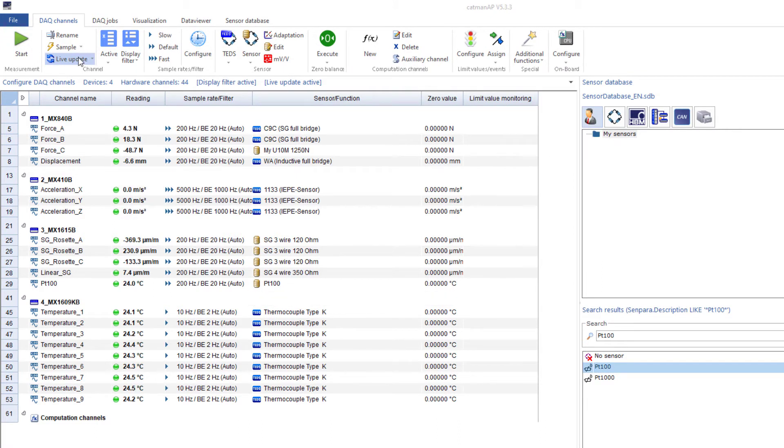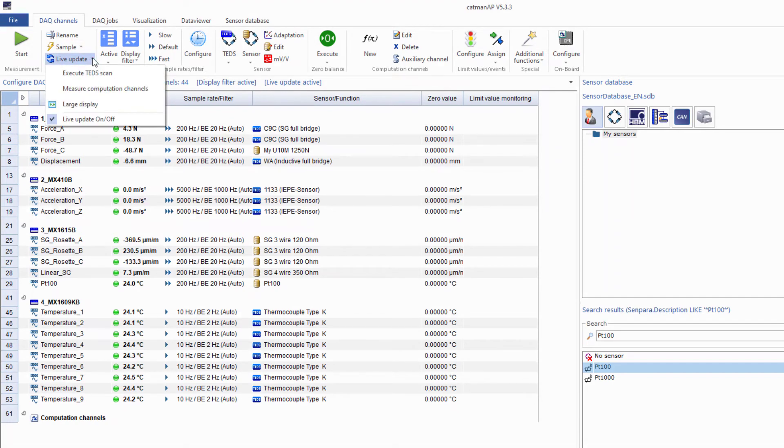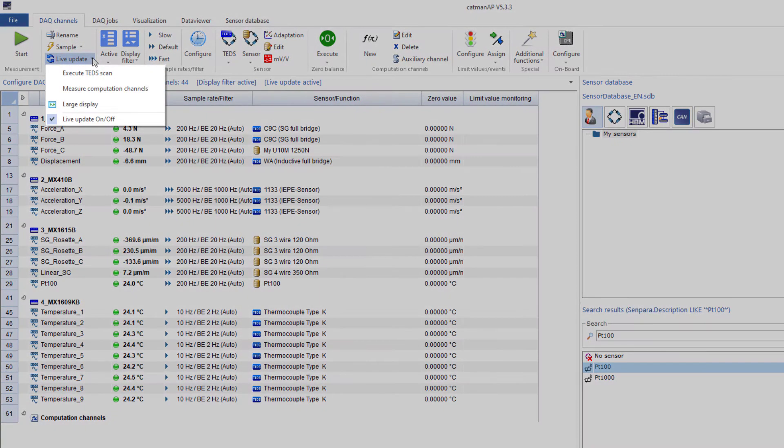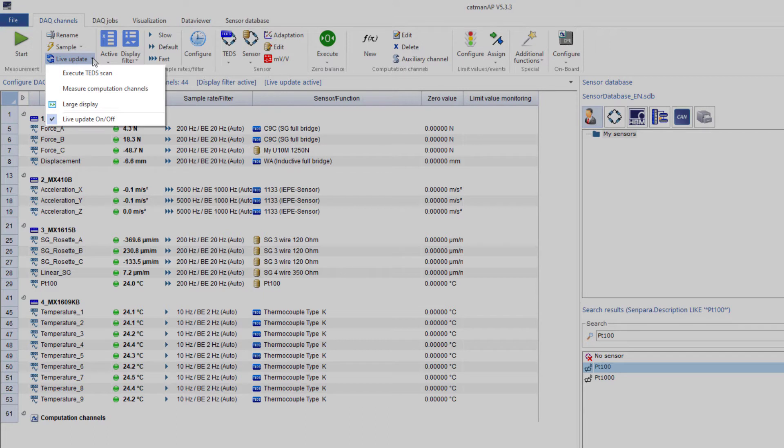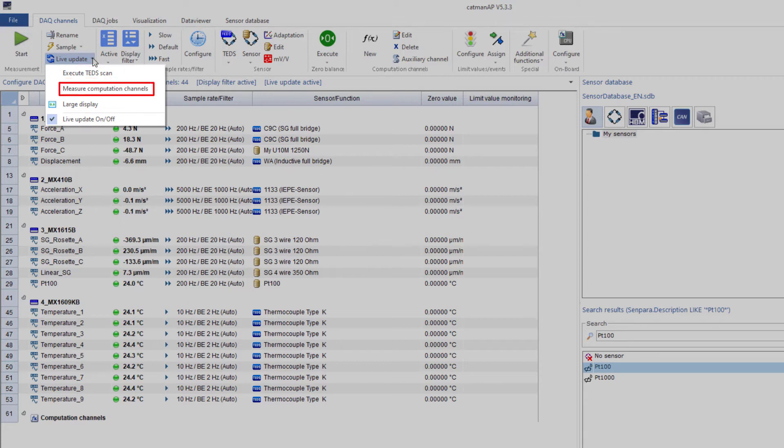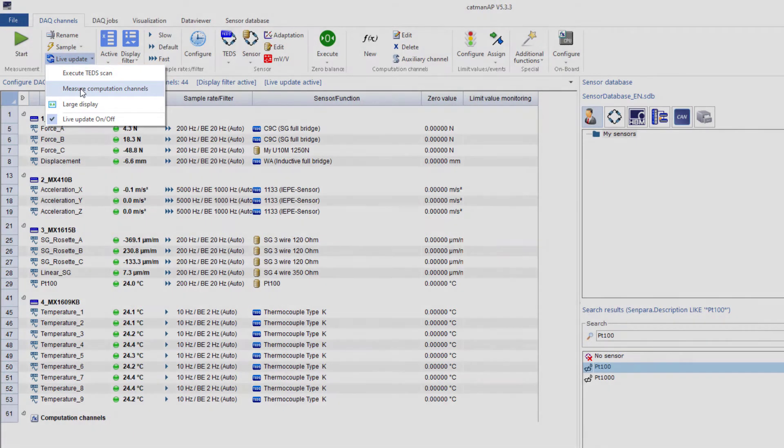If the channels do not yet provide measured values with your Catman version, you can switch on or off again the update with one click. If you have many channels in your measurement project, it is also a good idea to switch off this update. Catman will then have more time to take care of your inputs and will not need to constantly update all channels. Here, you can also switch on or off the TEDS scan or updating of the calculation channels. I'll activate updating of the calculation channels once.